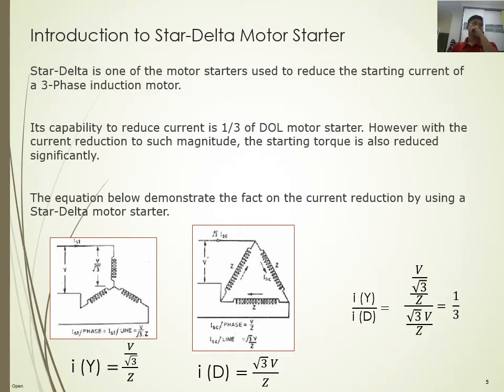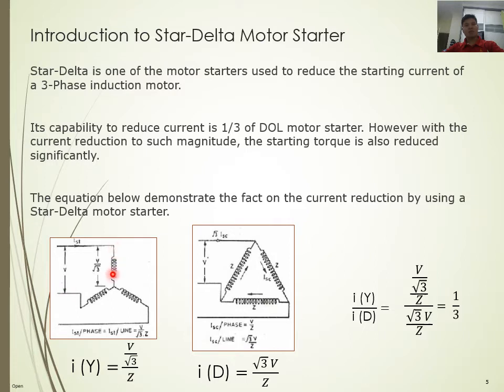This is the simple theoretical explanation for why the motor is started in star and then, once the motor has run for a certain period of time, converted into delta connection. In a three-phase circuit in star connection, the line-to-line voltage and the phase voltage differ by root 3. For example, the line-to-line voltage is 415V and the phase voltage would be 240V.